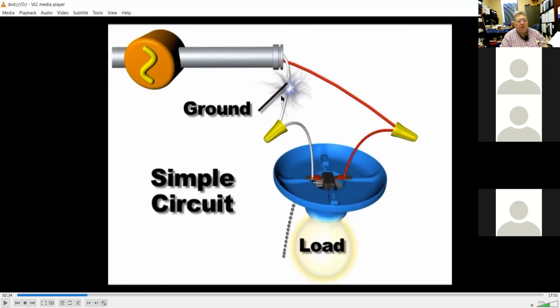And when it gets back to the panel, those of you that are taking the residential class know that when you take the face of the breaker panel off, you have a ground bar on the left and a neutral bar on the right. All of your neutrals, when you get back to the main panel, get connected through a tie bar to the ground bar. So neutral, when it gets to the final destination, does go to ground, and they're referring to ground here, but it's a neutral that goes to ground. Okay, so I just wanted to clarify that. And they're not showing just a regular ground wire out here because that's a plastic fixture, and there's nothing metal there to ground it to. But if you have a metallic type fixture, then the framework of it would have a ground wire.